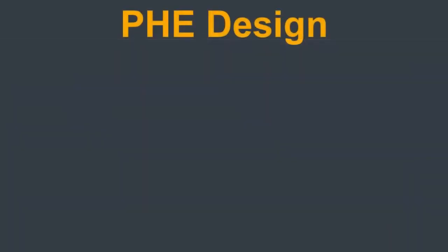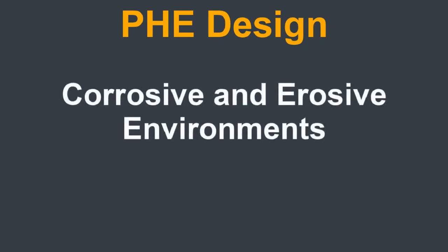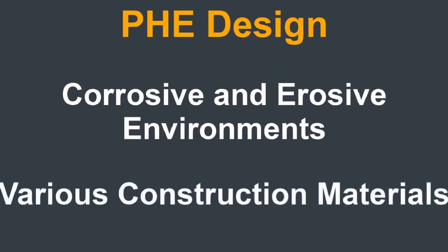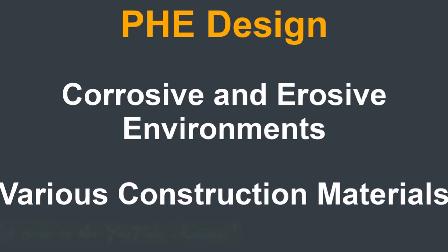Because plate heat exchangers are used for wide-ranging applications, they must be designed to withstand the process conditions in which they operate. This may include corrosive and erosive environments. It's possible to construct plate heat exchangers from various materials, including metals, alloys, and plastics. Different materials make the plate heat exchanger more suitable for different applications. For example, if a particular flowing medium reacts aggressively when coming into contact with certain metals, polymer-based materials such as Teflon may be used instead.